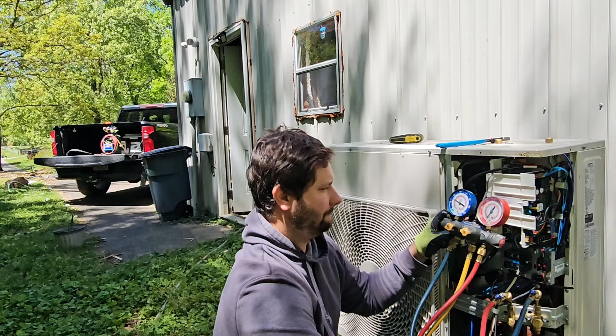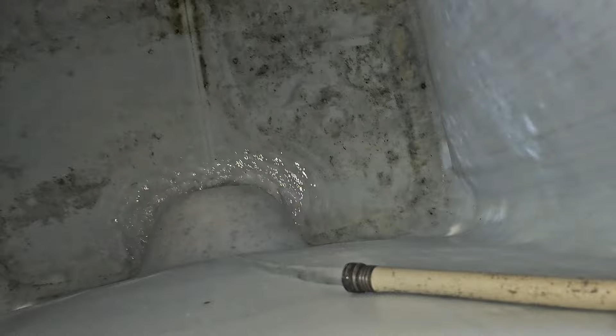All right, valves are closed on the unit. We'll open those up after we do a vacuum. We got 300. We're going to let it set on 300 for at least 30 minutes, and I'm going to soap test all of my fittings. Filling the IBC tote up with water is going to be another good way for us to leak test, because once we get water over all of our connections, if we see any bubbles, then we know we've got a leak. But so far, no leaks.